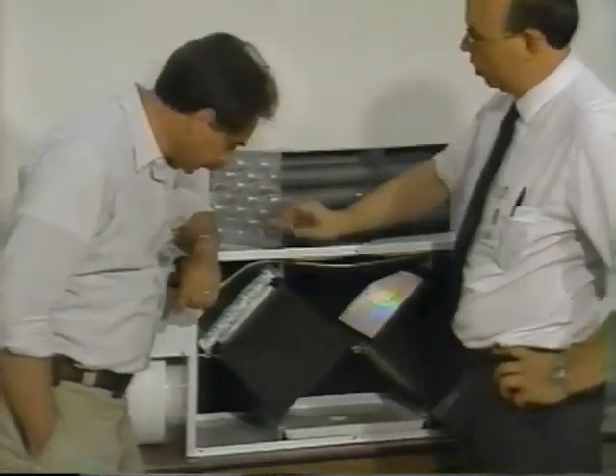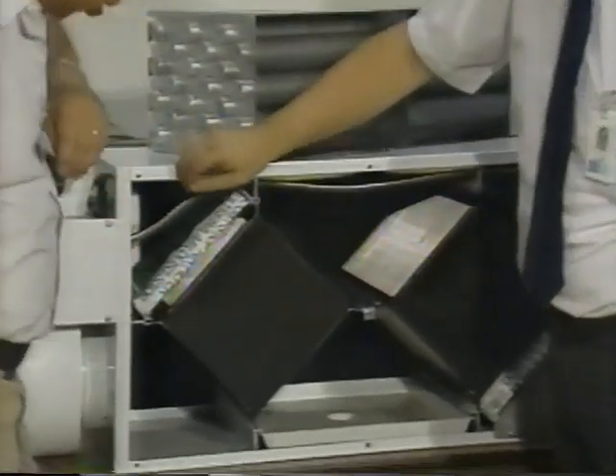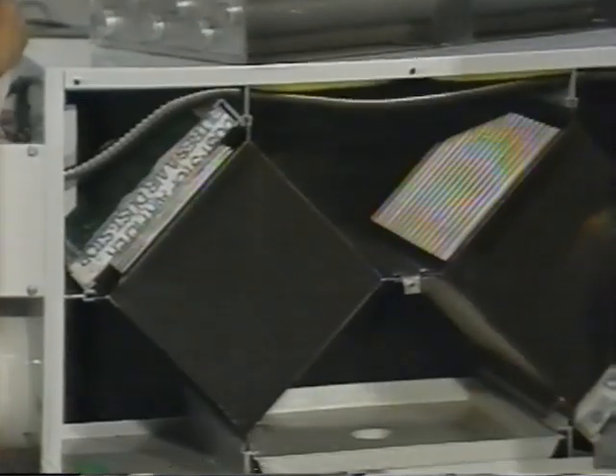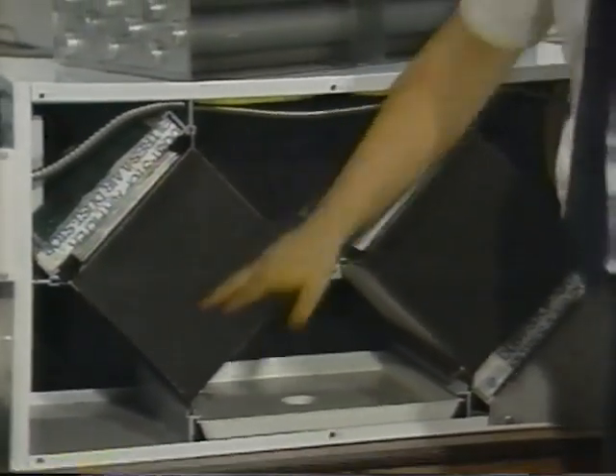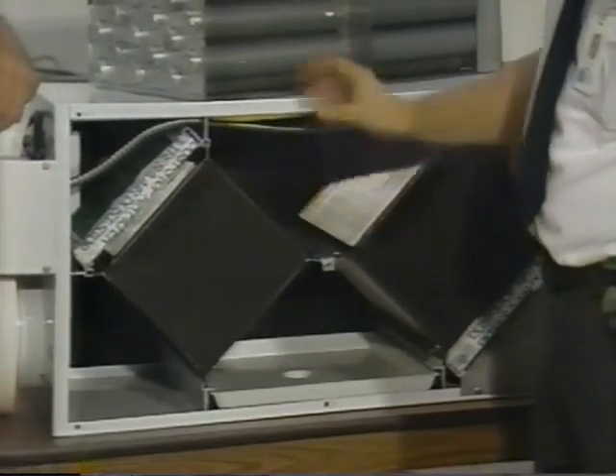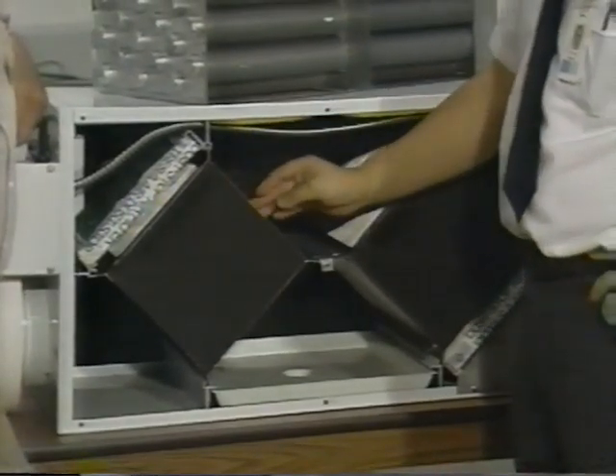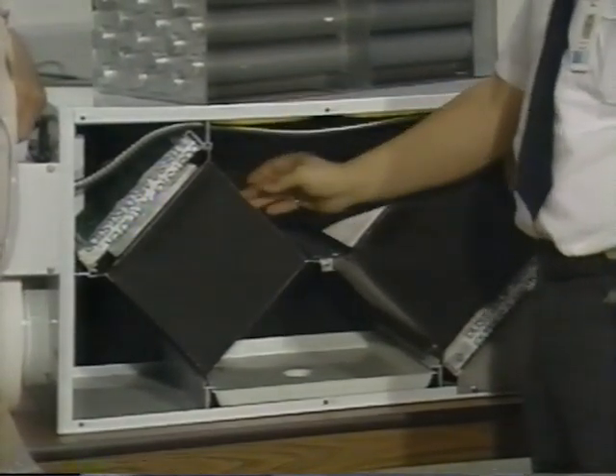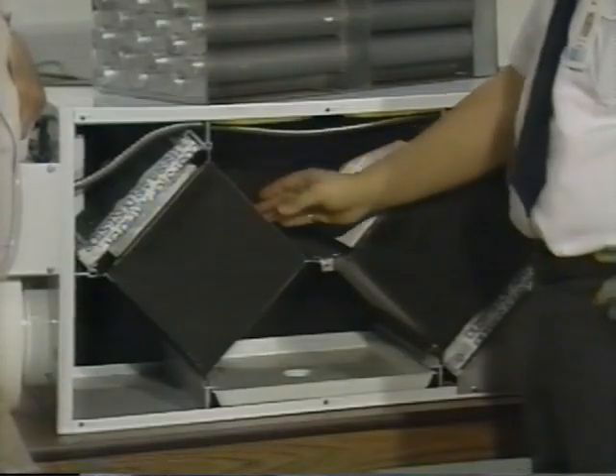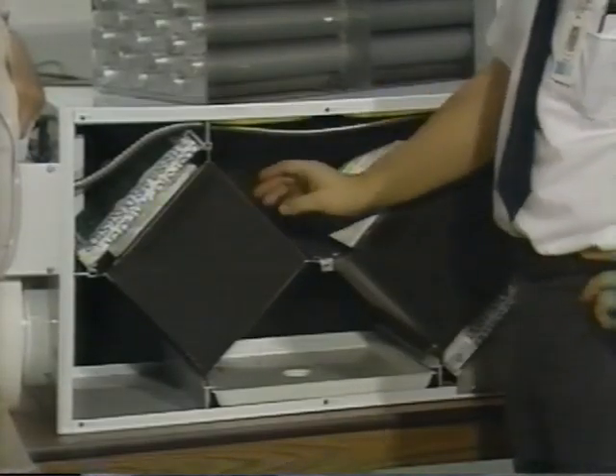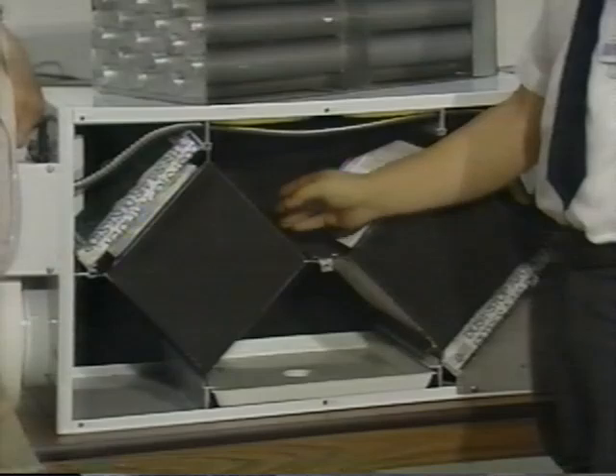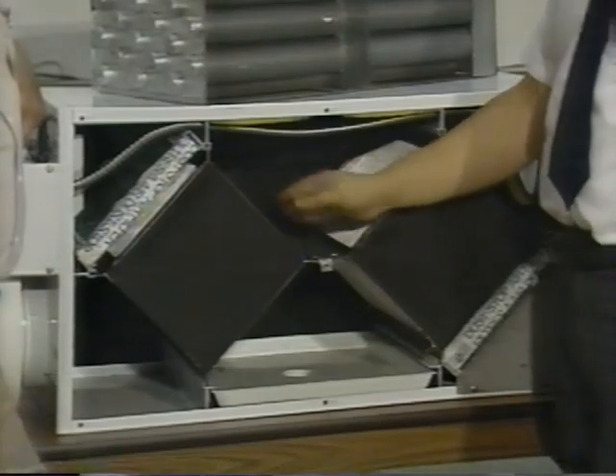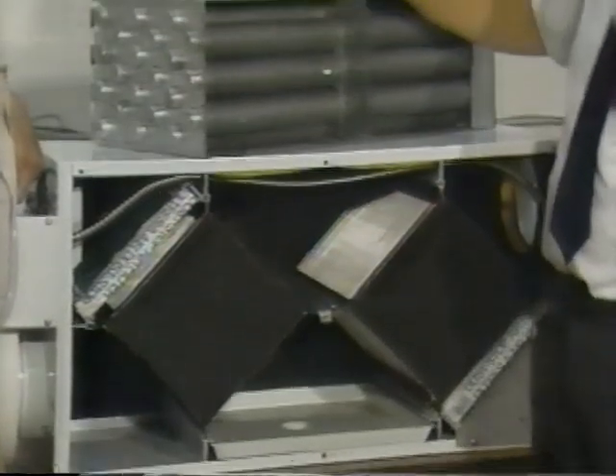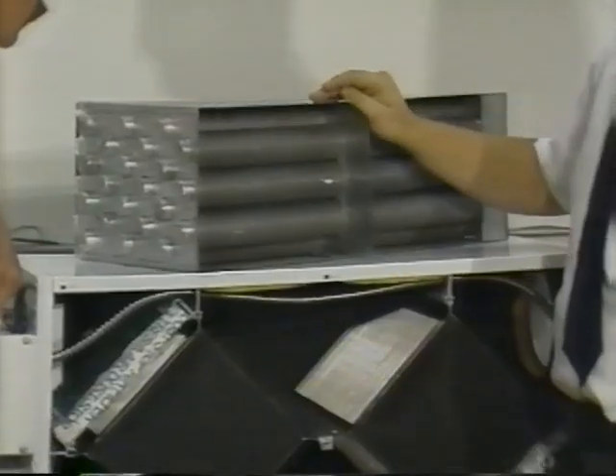What happens is the warm exhaust air from the house comes out through the unit, out through these cores into the outside. The cold, fresh air is brought in through the cores and dumped into the house. As the two air streams pass by each other in the cores, the heat is transferred from the warm exhaust air to the cold supply air so that it's preheated when it comes into the house. This type of core is plate type, which is quite common. We also have the heat pipe type core, which is another one of the common ones.